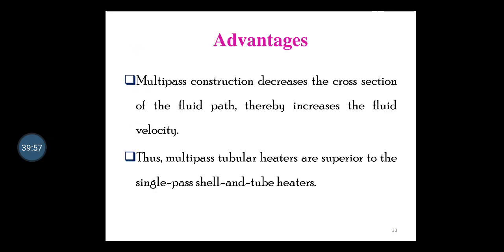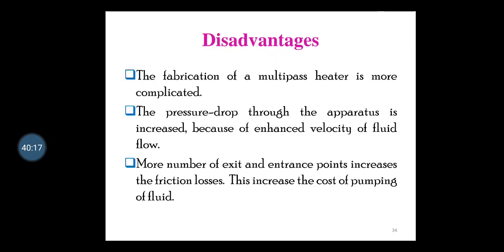As far as the advantages of this multi-pass heater are concerned, the multi-pass construction decreases the cross-section of the fluid path, thereby increasing the fluid velocity. Thus, multi-pass tubular heaters are superior to the single-pass shell and tube heaters. As far as the disadvantages are concerned, the fabrication of the multi-pass heater is more complicated and the pressure drop through the apparatus is increased because of the enhanced velocity of the fluid flow. The third disadvantage is that more entrance and exit points increase the friction losses. This increases the cost of pumping fluids.